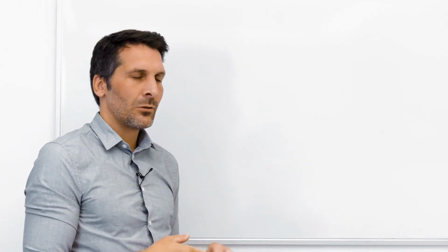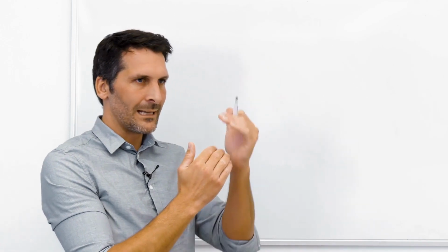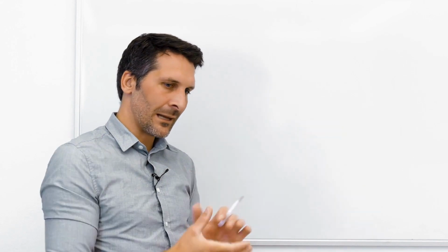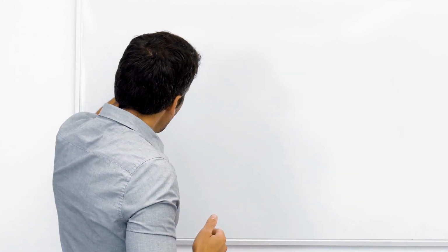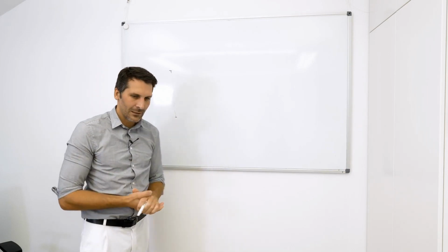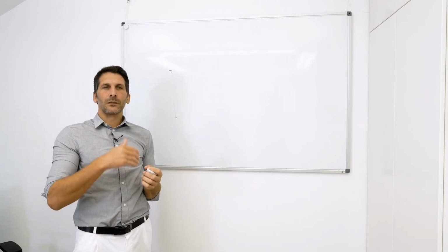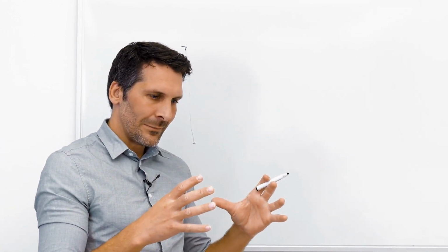The implant is there to first create the basic prerequisite so that you can lengthen. You are only lengthening the bone with the implant. That means the implant is supposed to stabilize the bone in 3 dimensions and ensure the precise lengthening speed. So on one side, you have the implant that is embedded in the bone. We have an initial length here, and this initial length of the bone is to be lengthened. That's the basic idea.